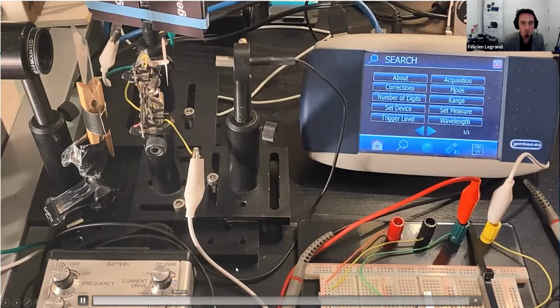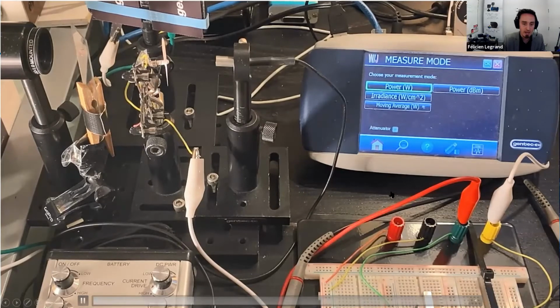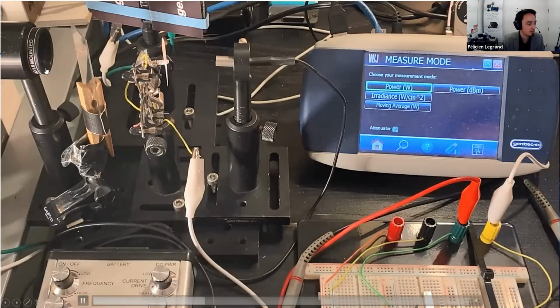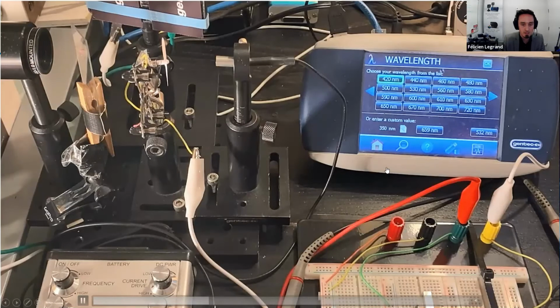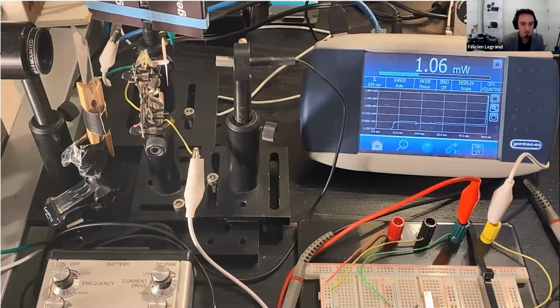First, I need to tell the device which mode I'm going to use. I want to measure power, and I'm going to check the attenuator box, because I'm using an ND1 filter on this photodiode. I simply need to tell the device to multiply the signal by 10. Then select the wavelength, the 659 nanometer red laser diode. I'm going to tell the device the wavelength to get a calibrated measurement.